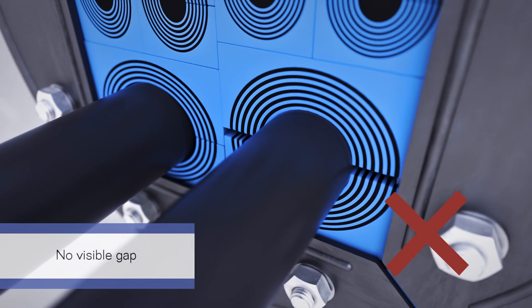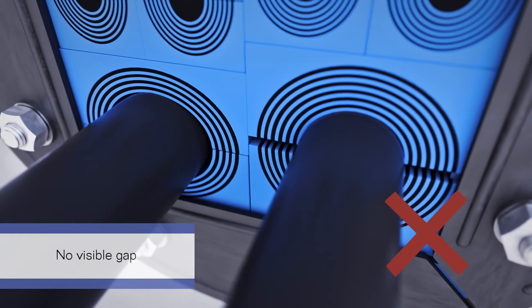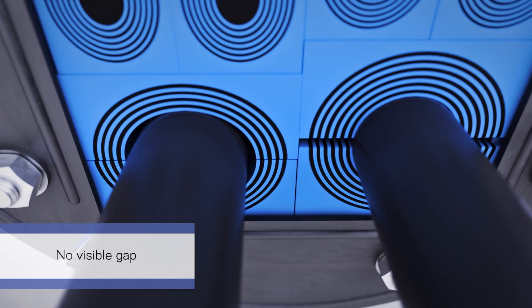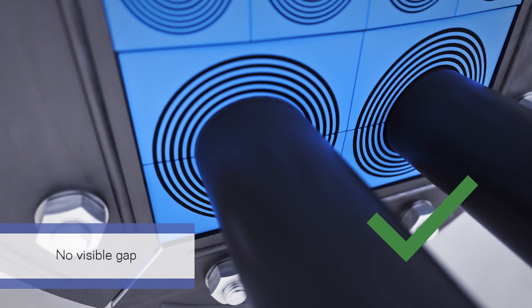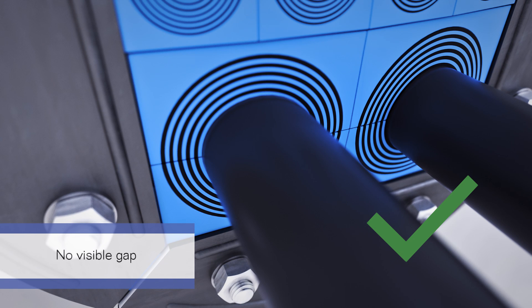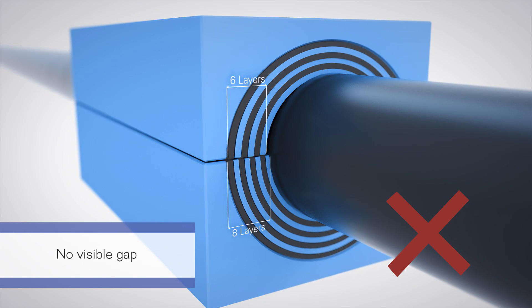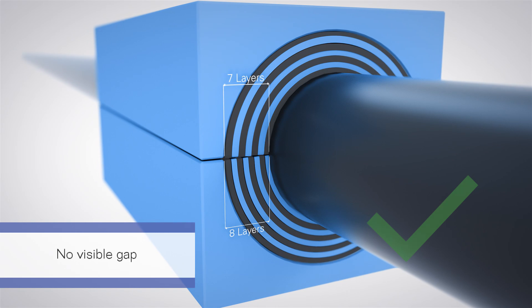Check that there is no visible gap after compression, neither between the cable or pipe and the module, nor between module halves or between the modules and the frame. The peeling of the module halves may not differ by more than one layer.